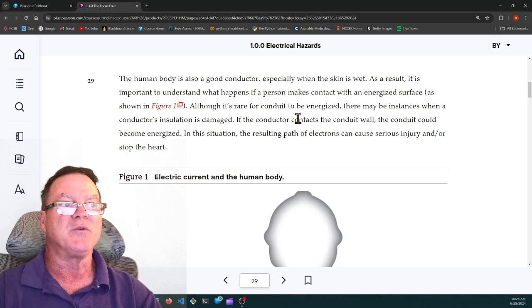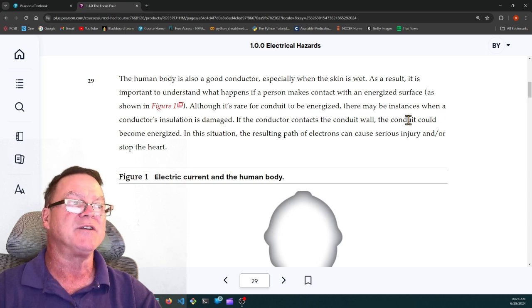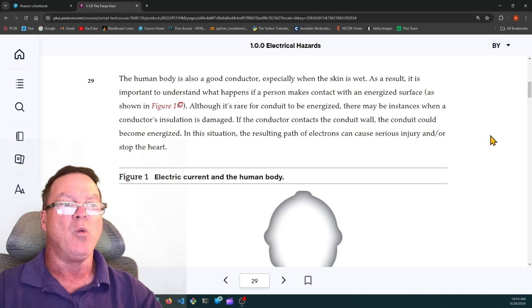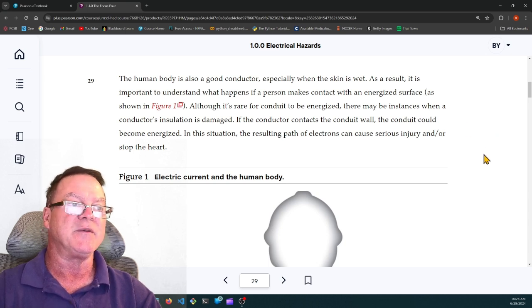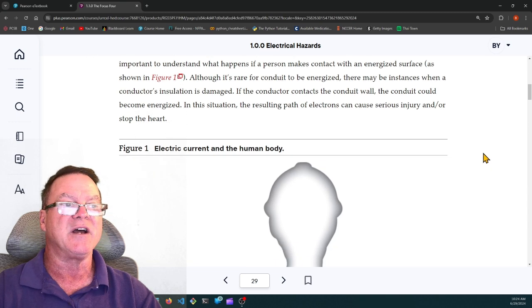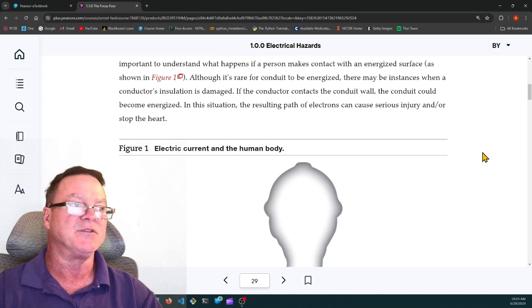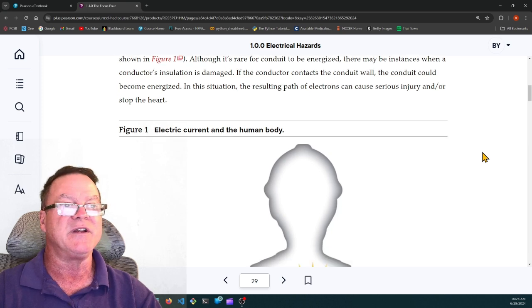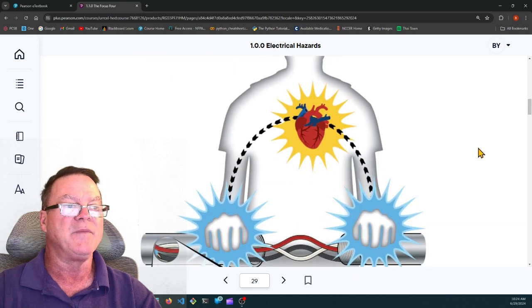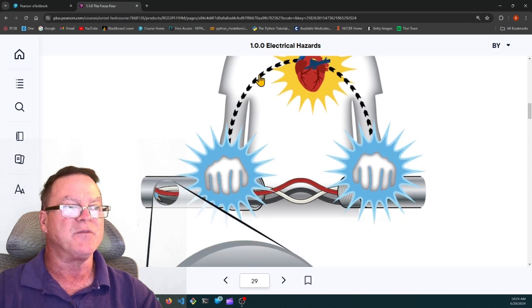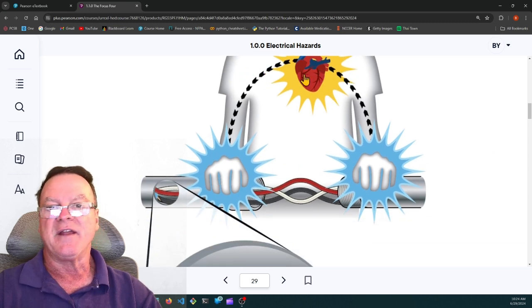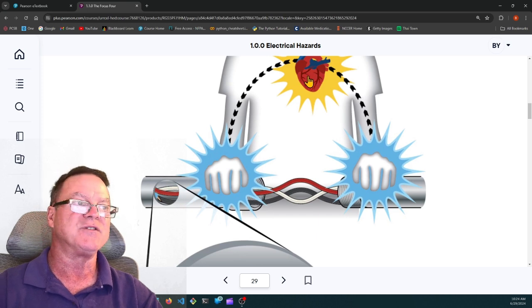As a result, it's important to understand what happens if a person makes contact with an energized surface, as shown in Figure 1. Although it's rare for conduit to be energized, there may be an instance when the conductor's insulation is damaged. If the conductor contacts the conduit wall, the conduit could become energized, and in this situation, the resulting path of electrons can cause serious injury and or stop the heart. So it all depends on what path the current takes through the body. If it goes from hand to hand and crosses the chest, that's the most dangerous path for electricity to flow through the human body.